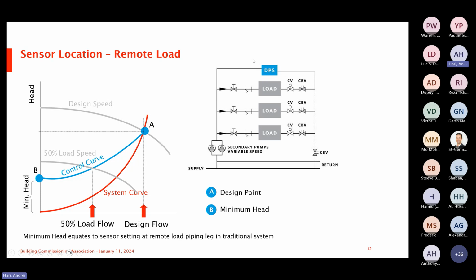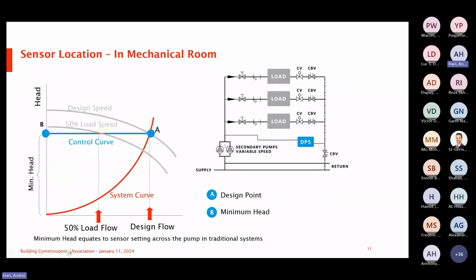So when that DP sensor is there, it's controlling the system. What happens then is that this may be my minimum head pressure, but at zero flow, let's say that this is 10 feet, okay, at zero flow, I'm good. But at this point right here, I'm going to need 15 feet to go through this loop. My pump says, oops, I'm satisfied. Good. Sorry.